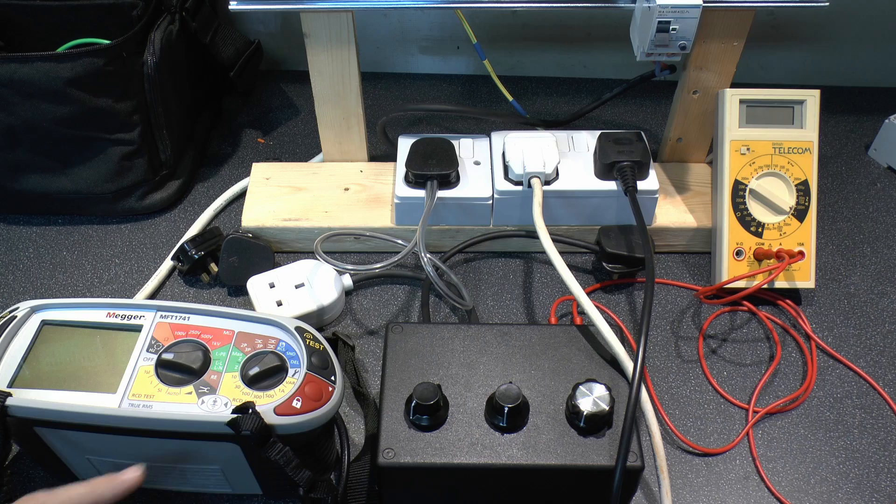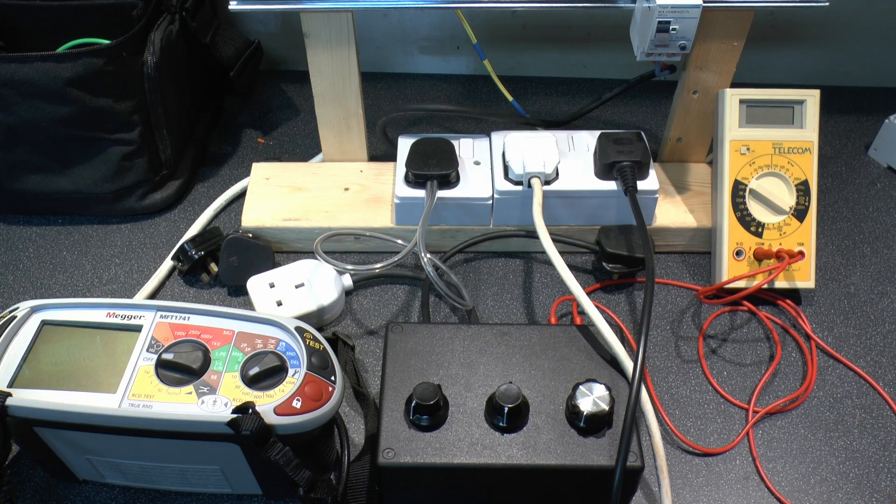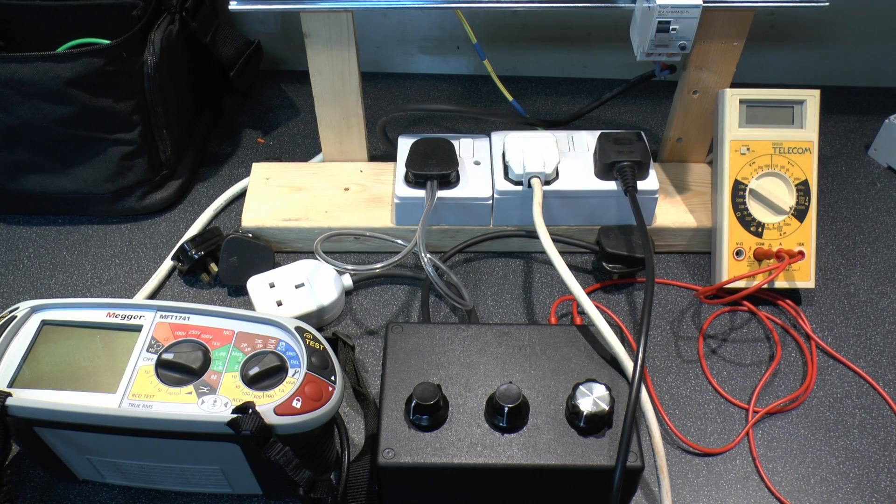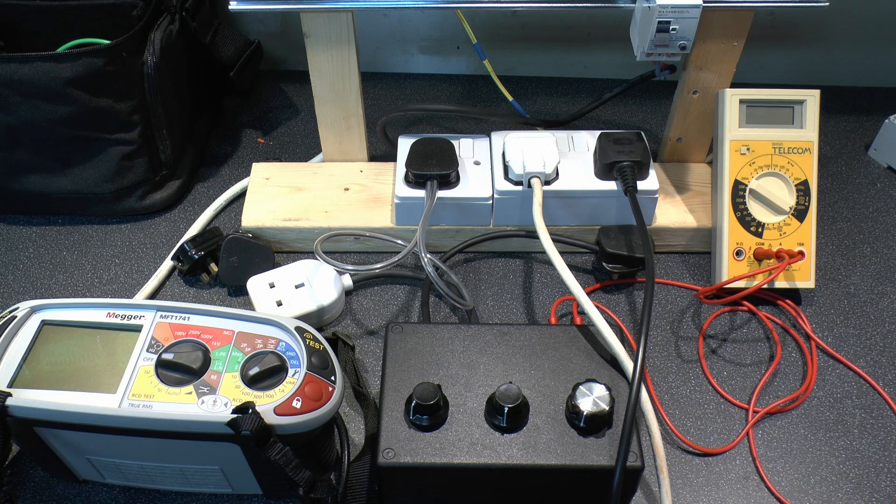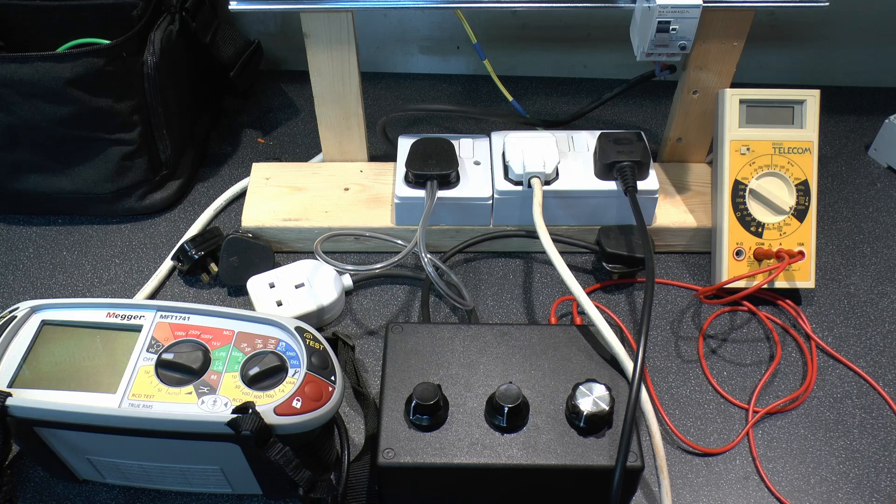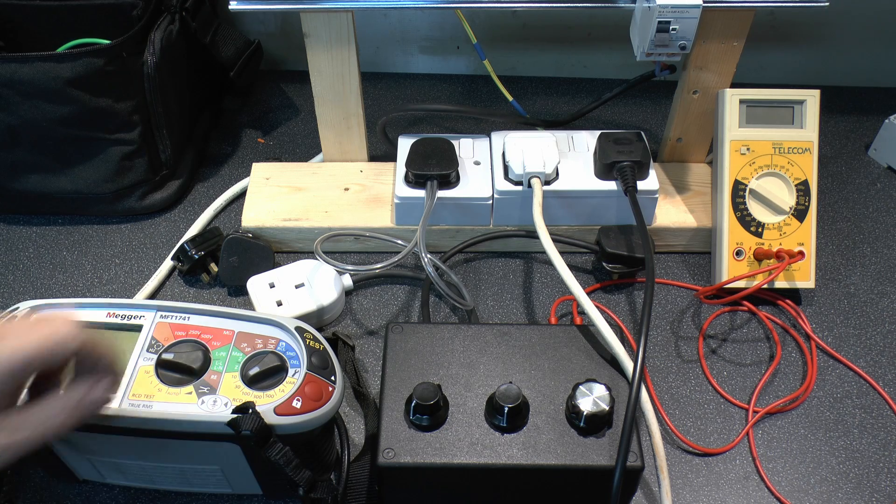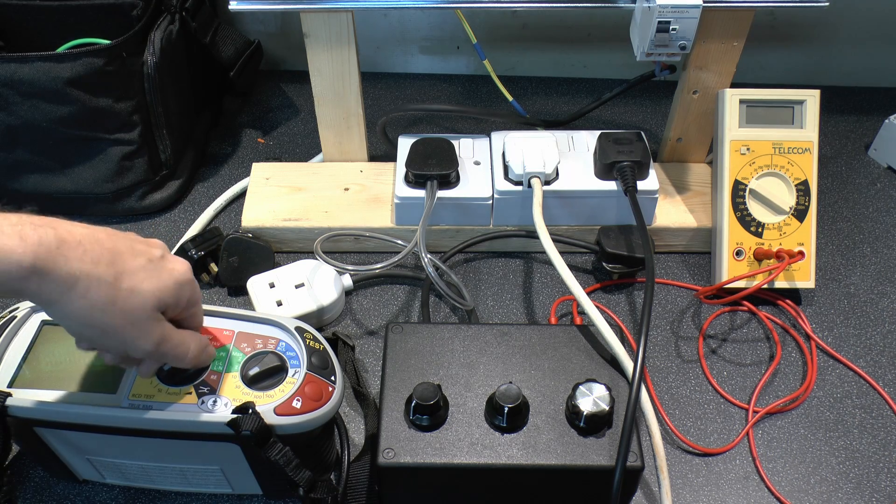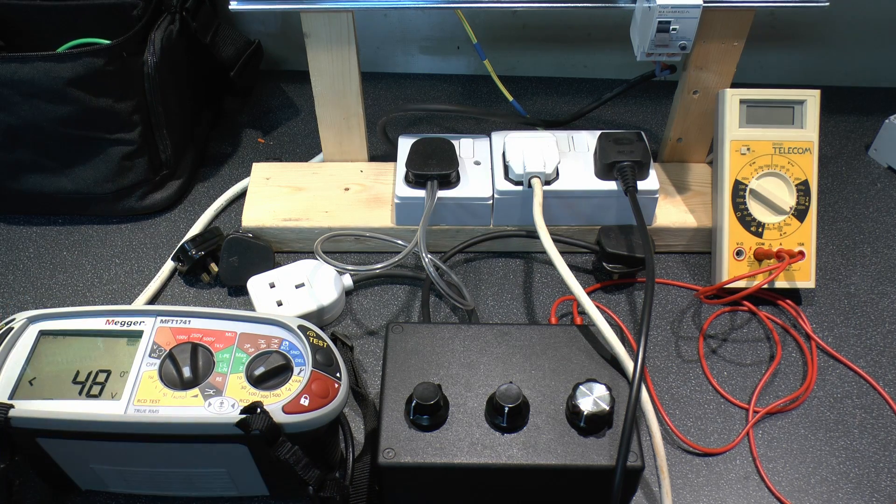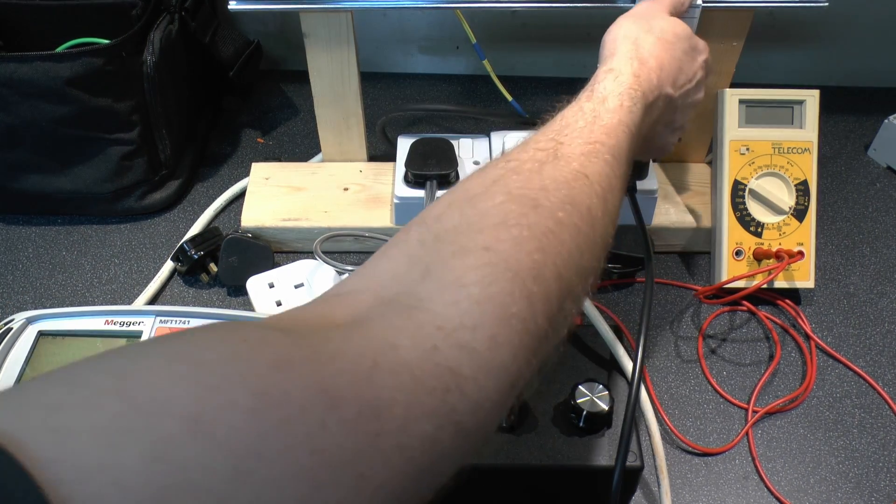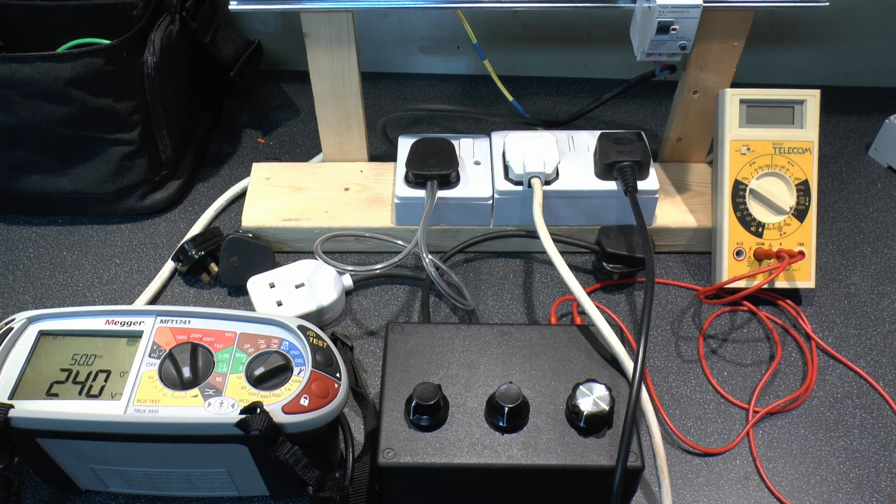Now to start with what we're going to do is just do a ramp test on this which will determine the current at which that actually trips. Now this is a 30mA RCD so it should trip somewhere greater than 15mA but obviously not greater than 30, so in that sort of range. So if we turn this on to the ramp testing position here and just put the power on as well, and we can turn on the RCD over there like that.